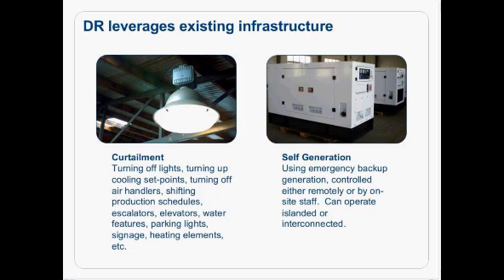The other way of enabling demand response is through backup generation. So using that backup generation, either controlled remotely by a grid operator or a third party like Enernoc, or controlled manually by on-site staff. Most self-generation for demand response is islanded using an open transfer switch. I'll talk about it in a minute. Some facilities do interconnect, and they do that for the reason Mike mentioned earlier regarding UPSs, where a facility can't have a brief interruption in their power. Sometimes they will operate interconnected to the grid, but by and large, a facility will shut itself off from the grid and operate independently.